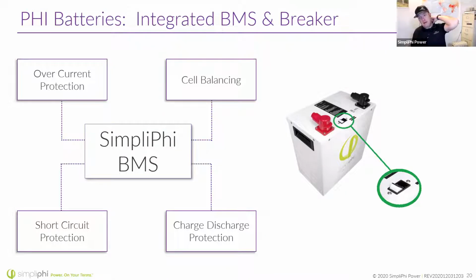All of the batteries also have a breaker. That's great for servicing batteries—you can turn them off and isolate them for troubleshooting. It also helps during install; you can shut a battery off and not risk shorting out the terminals if you're tightening down a lug with a wrench. Once everything is safe and aligned, you can turn those breakers back on.